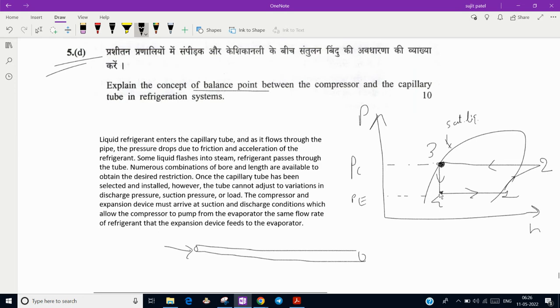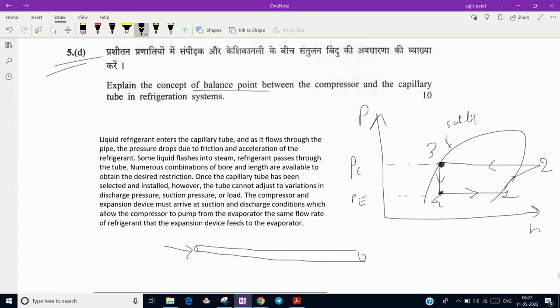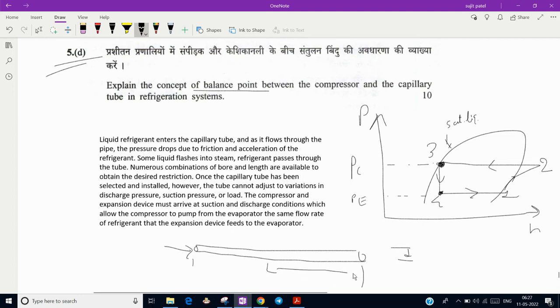Some liquid flashes into steam - point four is in the liquid vapor mixture, in wet region. So some portion of the refrigerant is already in vapor. We have to select the capillary tube such that this process will go on, but we have to think about the diameter and length.